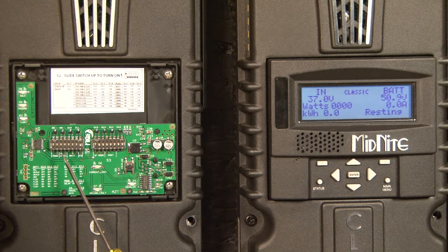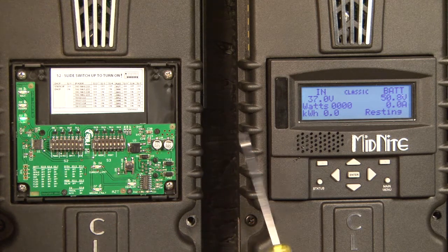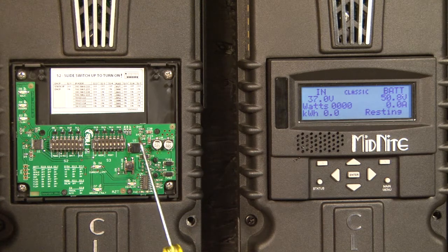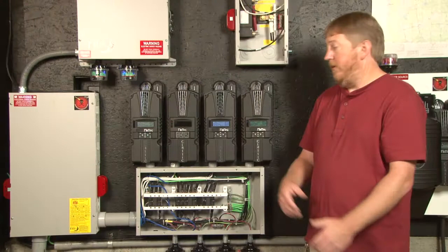I will say that with the switches standalone, this controller is set up to be a solar controller for a 12, 24, or 48 volt battery. If you want to use it for any other voltage battery or for any other input mode, you either need to interface it with an MNGP on a standard Classic, or program it with an MNGP in custom mode, or you need to hook it up to your computer and use the local application software we give you with the Classic Lite.